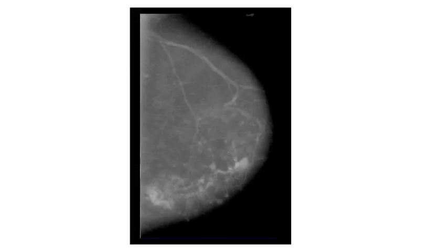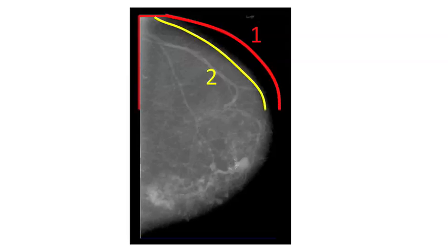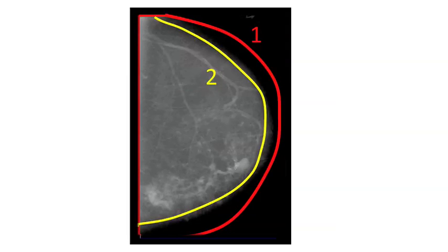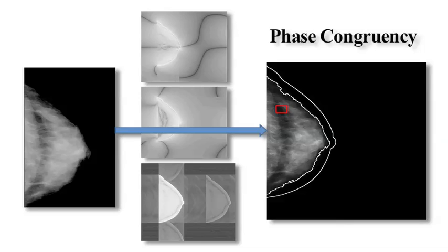There are two important tasks in a calculation of breast density. First, we have to identify the breast in the background on the digital image and then identify the part of the breast that is more or less uniformly compressed. The scientists at Matakina have developed a technique referred to as phase congruency — a mathematical approach used to identify the region of the breast that is uniformly compressed, over which the calculation of breast density is primarily carried out.